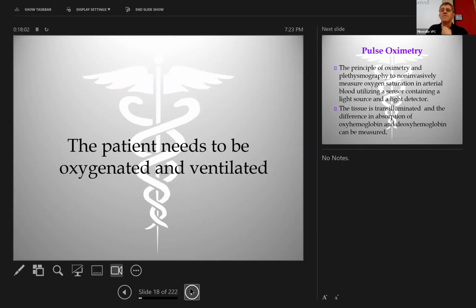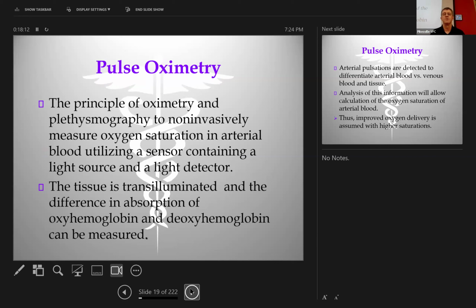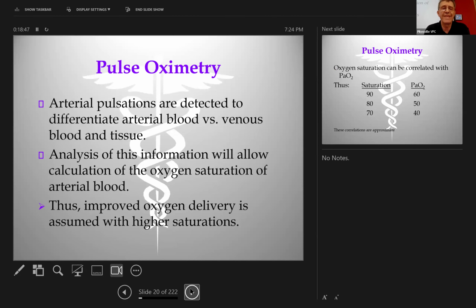That said, if you don't want to depend on your physical exam and you can do one thing and one thing only, what would it be? Pulse ox. We like pulse oxes. It's the principle of oximetry and plethysmography to non-invasively measure oxygen saturation within your arterial blood using a light sensor. It shines a red light at 2 wavelengths, 660 and 940 nanometers, and looks at absorption differences, and it will calculate it. Pulse oxes run a math formula, so they need a little bit of time to work. But they measure the difference of oxy versus deoxyhemoglobin within the blood in pulsatile vessels. Then it will take this absorption and calculate the saturation.